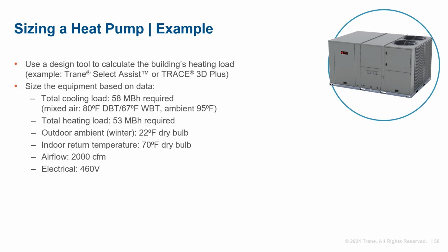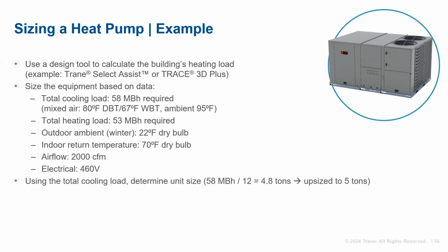For this example, we've determined the heating load to be 53 MBH. And for reference, the cooling load is 58 MBH based off the standard 80-67 entering conditions and the 95-degree Fahrenheit ambient, and the same CFM we are calling out for heating using the manufacturer's catalog or Trane Select Assist. Based on our cooling load of 58 MBH, we will need to determine the required cooling tonnage of our unit. Do this using a standard conversion formula of MBH over 12, which is tons of cooling. So for our example, that's 58 over 12 equals 4.8 tons. And to make this number neat, we round up to 5 tons.